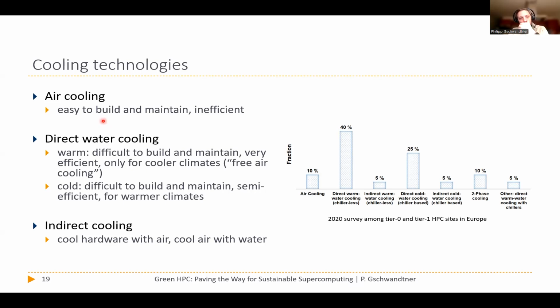If you really want to go into water cooling, there's warm and cold water cooling, and those differ in terms of how the water is cooled down. Both are difficult to build and maintain because water and electricity usually don't go along very well. But still, if you build it, you can have warm water cooling where you simply pump the hot water up to the roof of your building, for example, and use the ambient air without any additional means to cool the water down. That's why it's also sometimes called free air cooling.